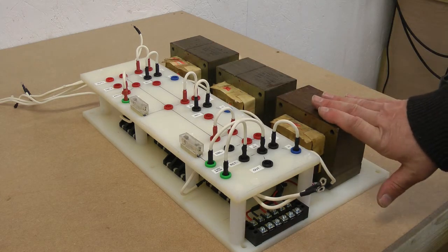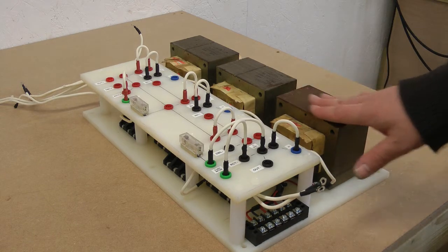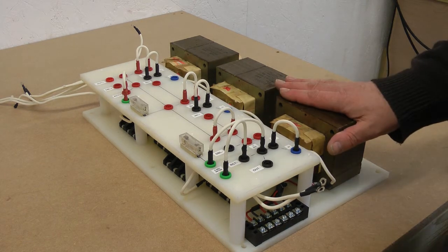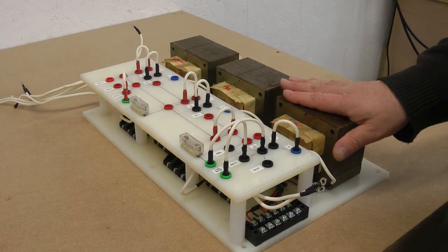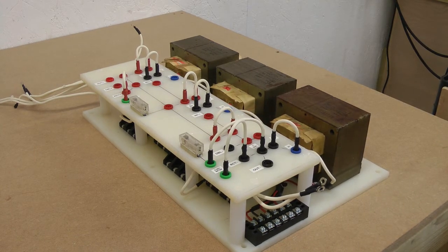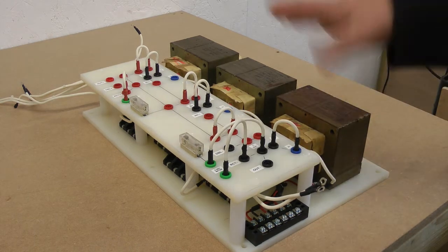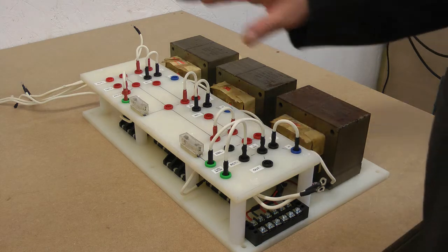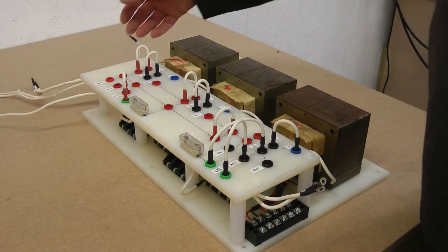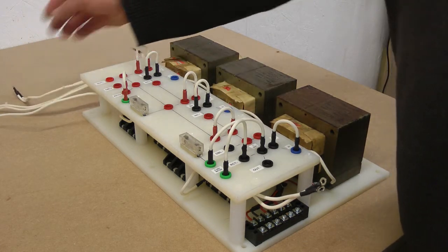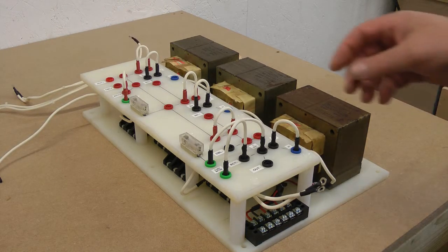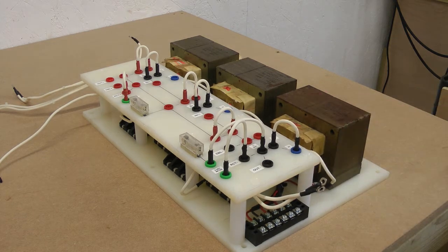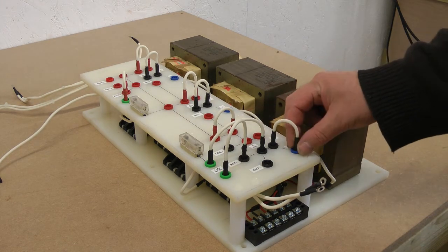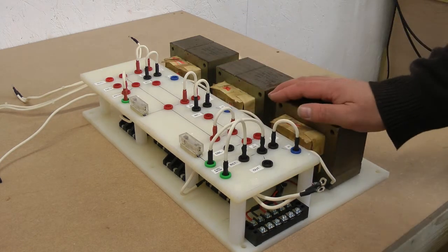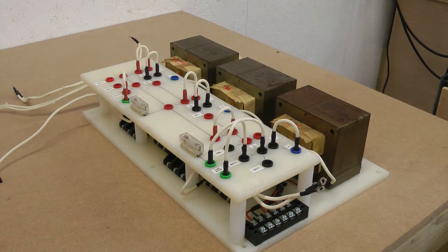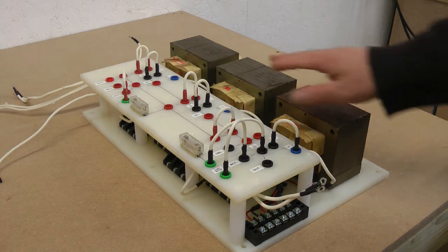And with microwave oven transformers, we are talking about very high levels of current. So these transformers can provide a heck of a punch, and in that respect, how we lay it out, how we wire it is very important. You can see that all the wiring that comes out of the switchboard that goes to the jumper panel, that goes to the back panel, and the various interconnects between the various boards, they're all done with 20 kilovolt AWG16 silicone wire. I've never really had a problem with this wire. It's very good at this kind of level, more than adequate for the type of currents that one's putting out on the secondary side.